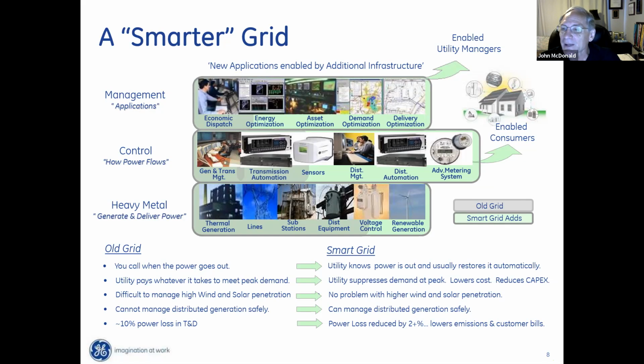So what we do today on an advanced distribution management system is integrate volt VAR control and do them coordinated. That's the part that's light green: integrated volt VAR control, IVVC, or sometimes we call it volt VAR optimization. We'll talk more about renewable generation. Let's go up here to sensors. Sensors is shaded halfway. We've been adding sensors to the grid for a long time. The challenge today is we have new specialized sensors that give us much more information. And utilities now have adopted what's called an observability strategy. Observability means: what information in my service area can I see at the control center? In other words, without having to get in a truck and go out in the field, what is observable remotely?